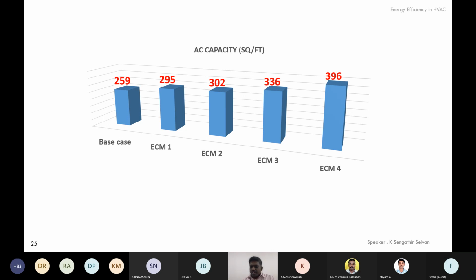In fact, even in a residential building, people just go with 1.5 TR, where your requirement is hardly 0.5 TR to 0.8 TR. And people feel that they get faster cooling, and that is actually very wrong. The additional capacity creates a large burden on the electric infrastructure, starting from your local area transformer towards the thermal plant that is generating the power. So it is prudent to analyze the air conditioning capacity selection, or OPEX selection, like this only.